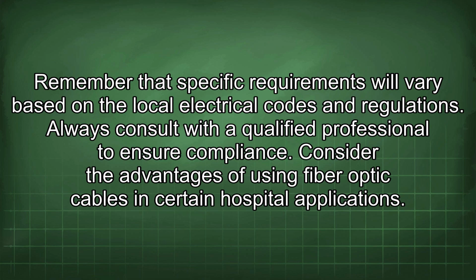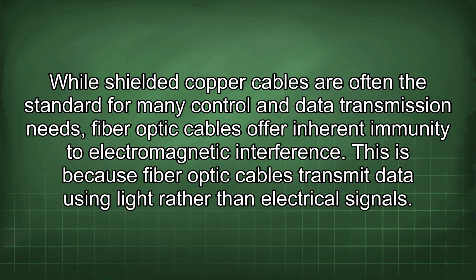Consider the advantages of using fiber optic cables in certain hospital applications. While shielded copper cables are often the standard for many control and data transmission needs, fiber optic cables offer inherent immunity to electromagnetic interference. This is because fiber optic cables transmit data using light rather than electrical signals.